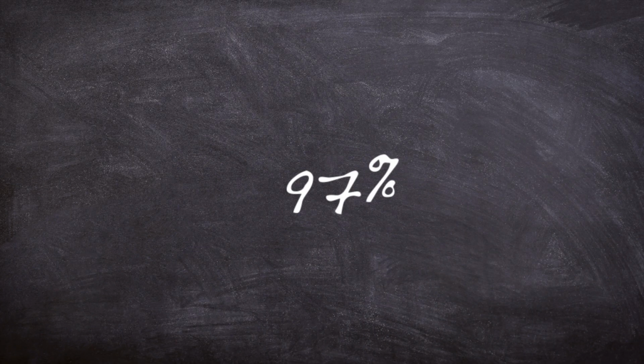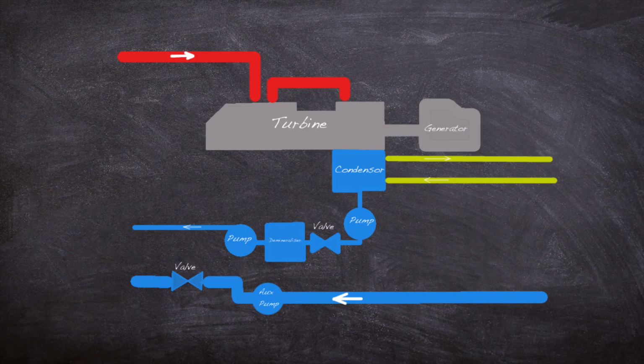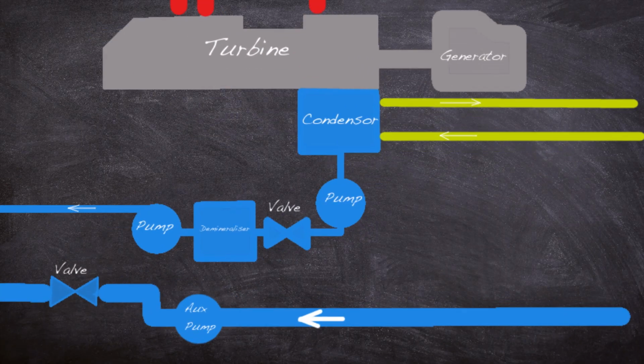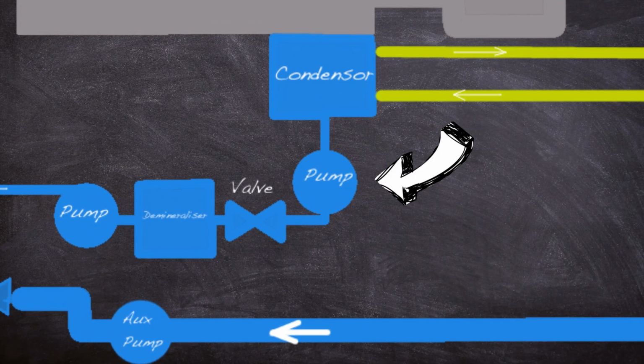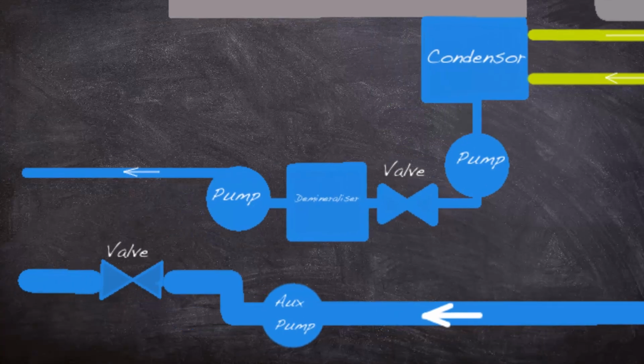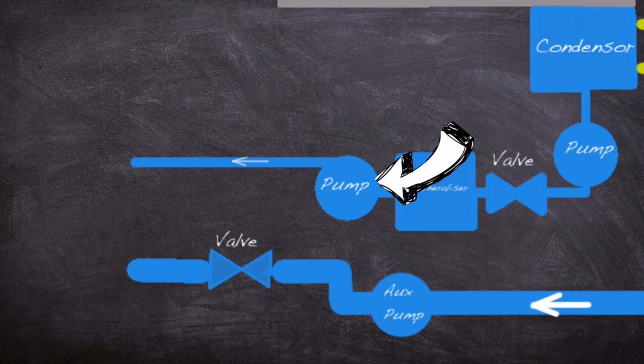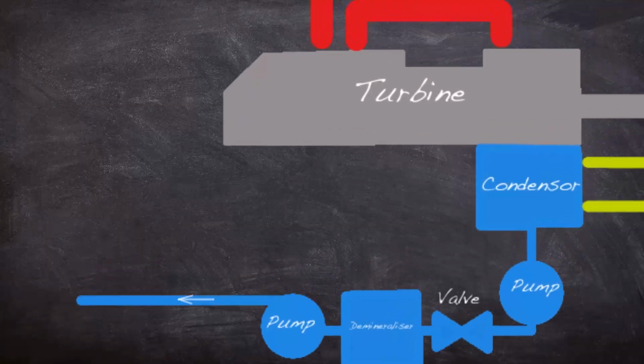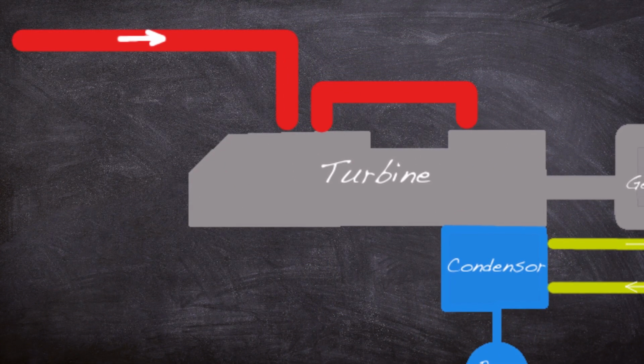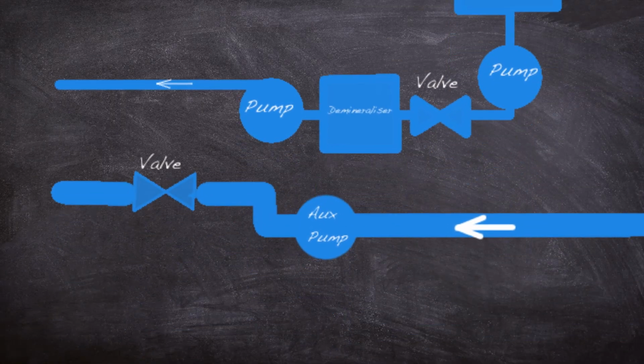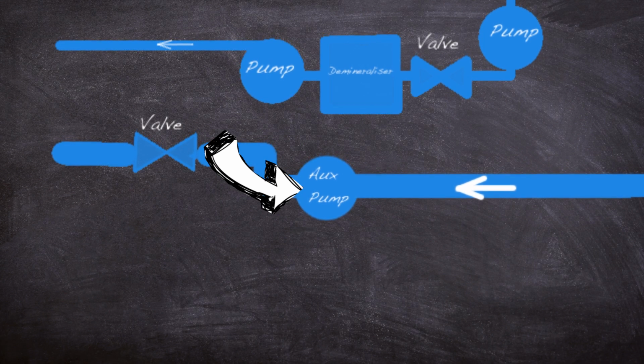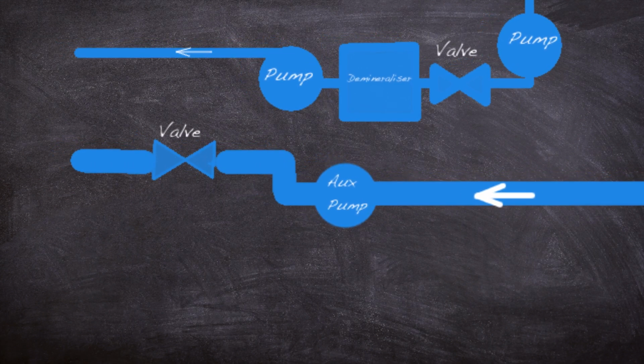On the 28th of March at around 4 a.m., TMI-2 was operating at 97%, whilst TMI-1 was shut down for refuelling. A secondary cooling system condensate pump tripped out, causing it to stop working. Lacking a water supply, the 2 feed pumps also tripped out. Due to the pumps on the secondary cooling system being shut down, a safety circuit automatically shut down the turbine generators. 3 auxiliary feed water pumps started up as designed.